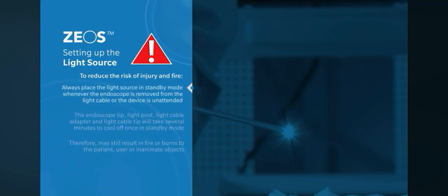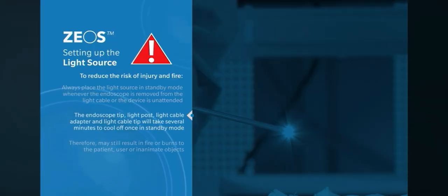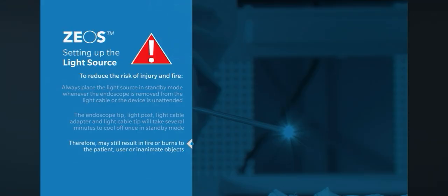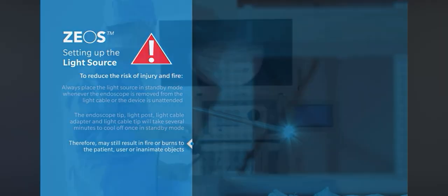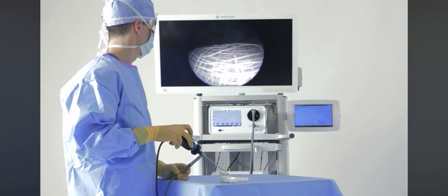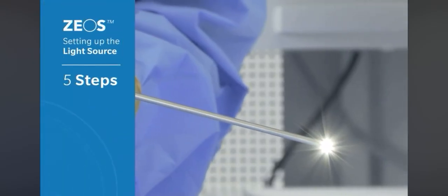Always place the light source in standby mode whenever the endoscope is removed from the light cable or the device is unattended. The endoscope tip, endoscope light post, light cable adapter, and light cable tip will take several minutes to cool off after being placed in standby mode, and therefore may still result in fire or burns to the patient, user, or inanimate objects. When using the internal light source, there are 5 steps involved with setup.